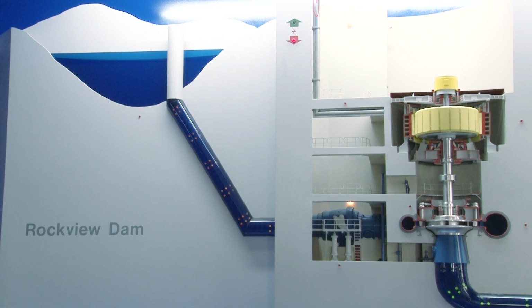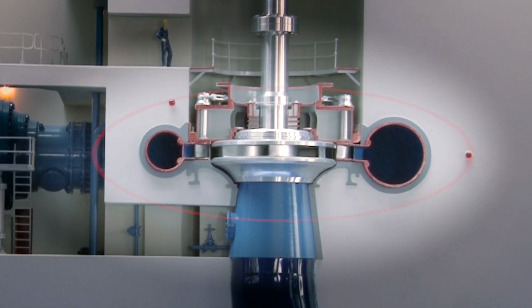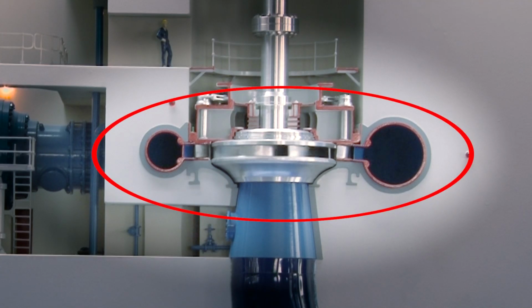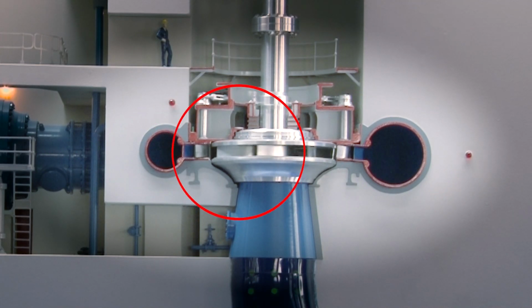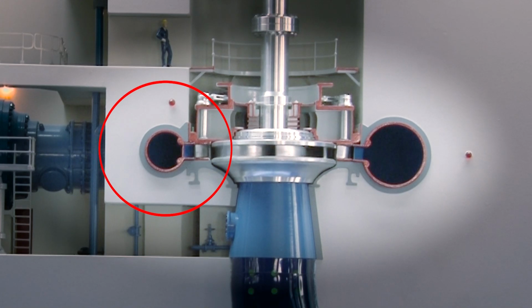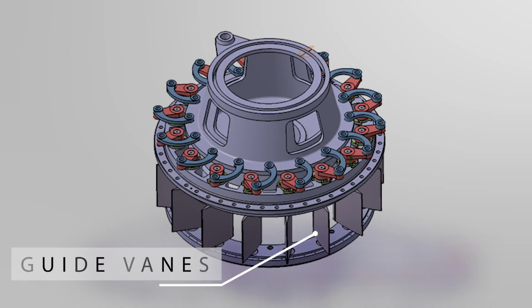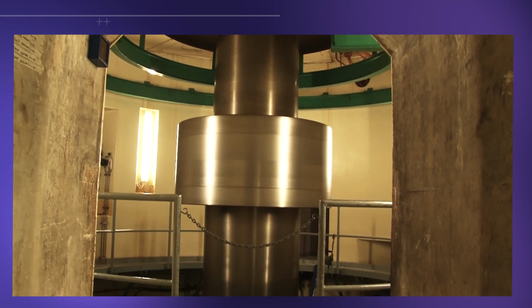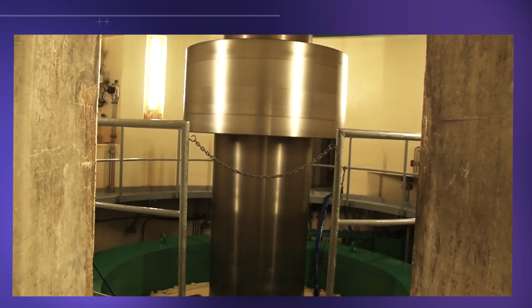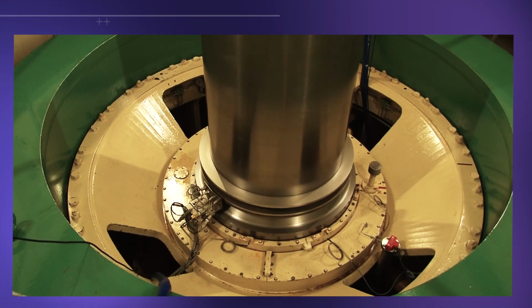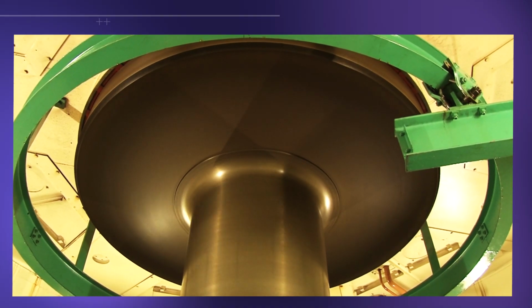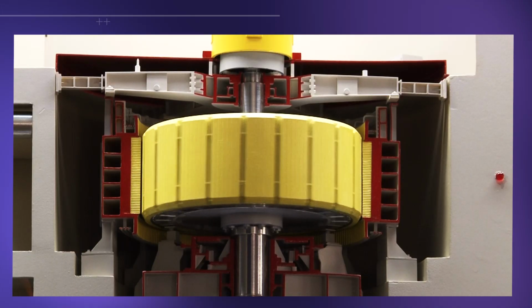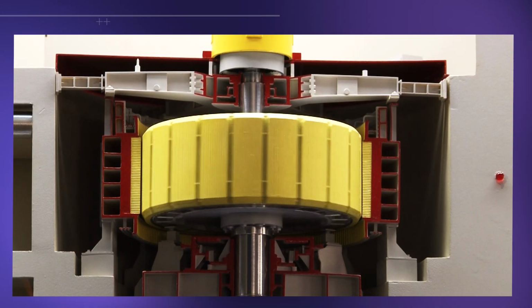The water passes into a spiral casing, which is a pipe that spirals around the turbine. As it spirals, the pipe narrows, building up pressure. Around the turbine are 20 guide vanes, which regulate the flow of water onto the turbine. The turbine always has to spin at exactly 300 revolutions per minute. The water pushes the blades of the turbine, which turns the shaft, which in turn spins the rotor in the stator, which then generates the electricity.